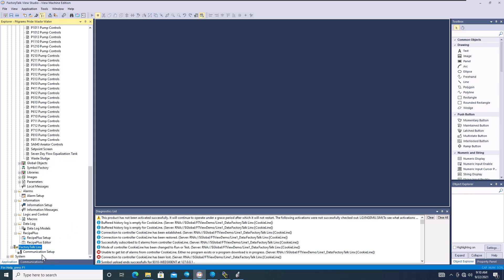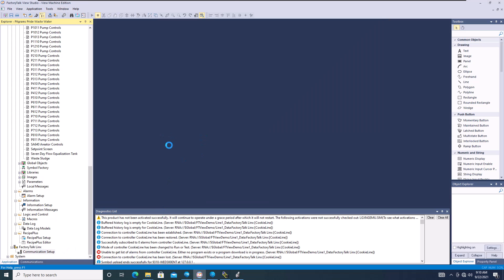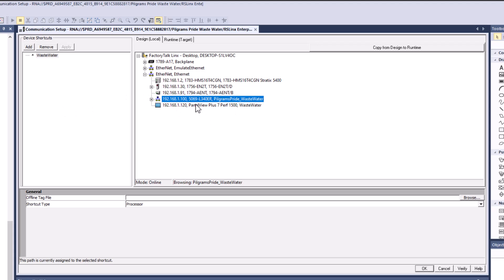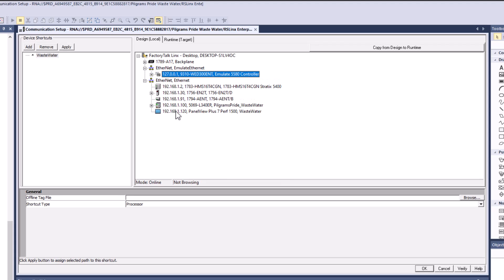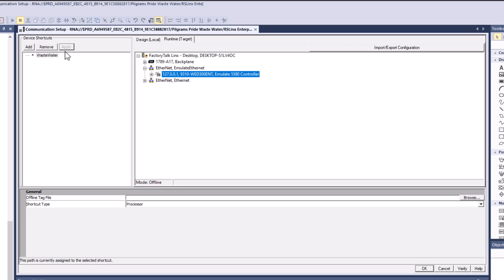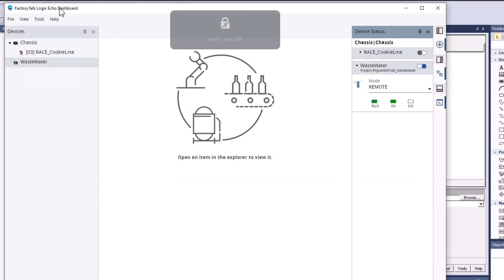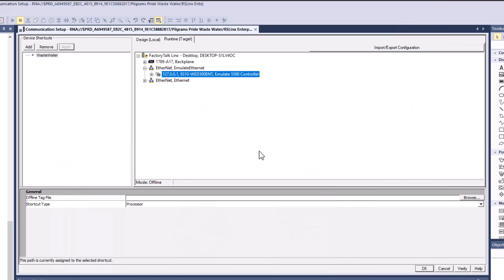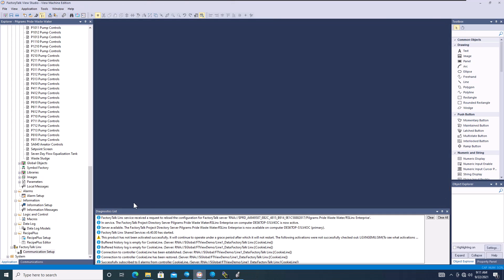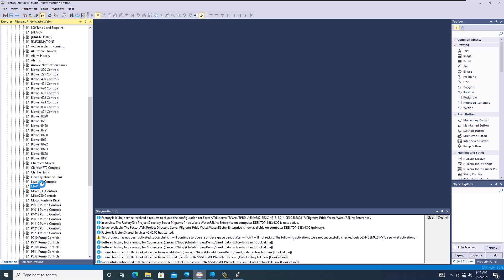Now we need to update our tag database in the HMI. We go to FactoryTalk Linx, then communication setup. In communication setup, we click on our shortcut — it's currently pointing to the original field directory. We're going to change that to our emulator and click Apply. We'll also copy that to runtime, since this is an ME application and we may want to run the runtime as well. Now both the design and runtime are pointed to the Factory Talk Logix Echo dashboard, which acts as the conduit. Verify connections and click OK.